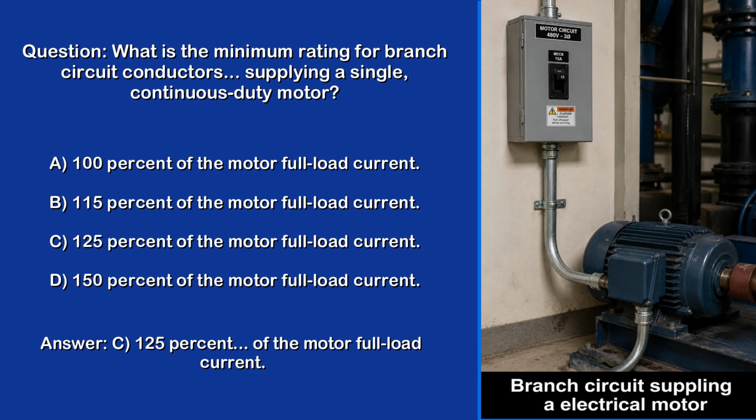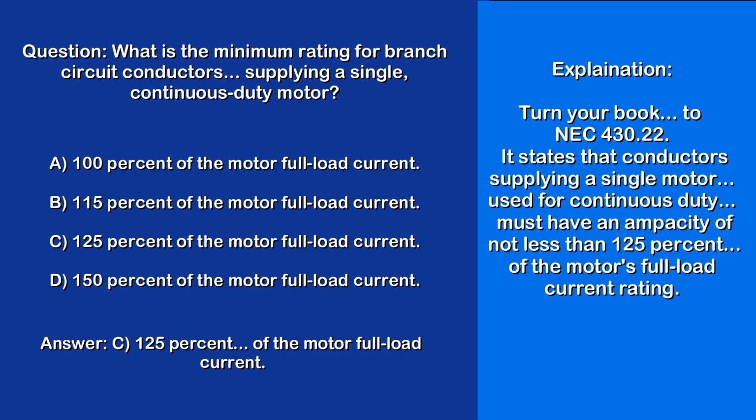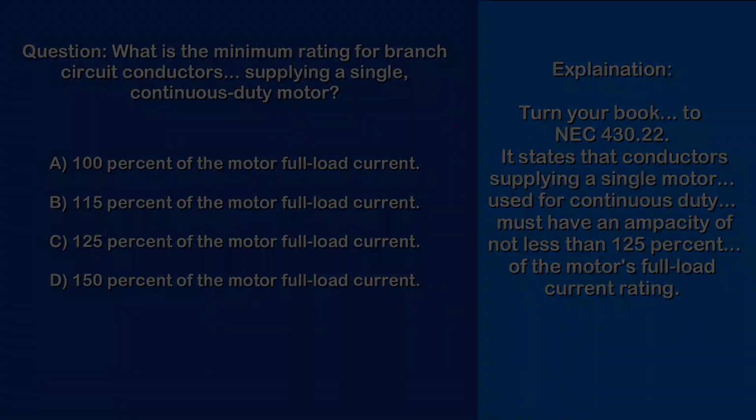Answer. C. 125% of the motor full load current. Explanation. Turn your book to NEC 430.22. It states that conductors supplying a single motor, used for continuous duty, must have an ampacity of not less than 125% of the motor's full load current rating.